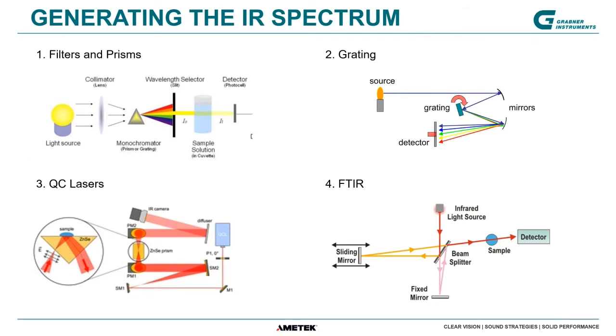So how is infrared spectroscopy working? There are basically four techniques which you can apply to disperse the radiation or energy to see which characteristic energy was absorbed by the components. Each technique has unique advantages and limitations. The first and simplest are filters and prisms — the most inexpensive method. Prisms only work around the visible range, but filters are widely applicable from X-ray radiation up to very long wavelengths, including far infrared. Then you have grating mirrors — specially designed mirrors that, depending on the angle of reflection, reflect different energy bands of the radiation. They are quite flexible over a wide range but tend to have glitches at certain wavelengths.